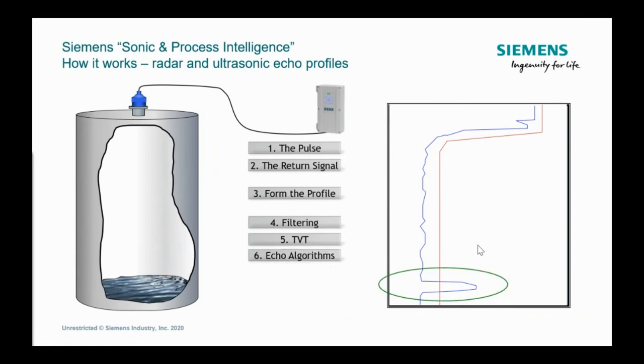Then it's going to apply something called echo algorithms. We have a couple slides coming up talking about that in a little bit. And then finally, it's going to make the selection for the echo. The instrument is going to go through these seven steps each and every time it makes a measurement. Okay, that's important. Sometimes that measurement is several times a second. Sometimes it's several seconds between measurements, just depending on the instrument and the type of application.